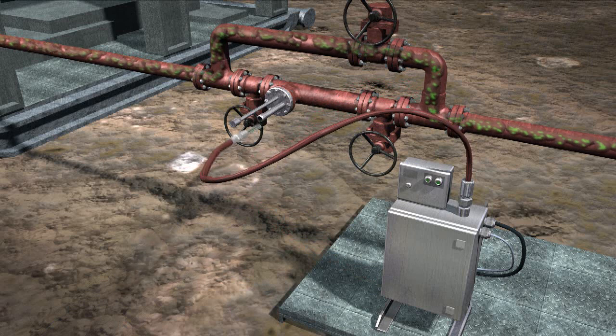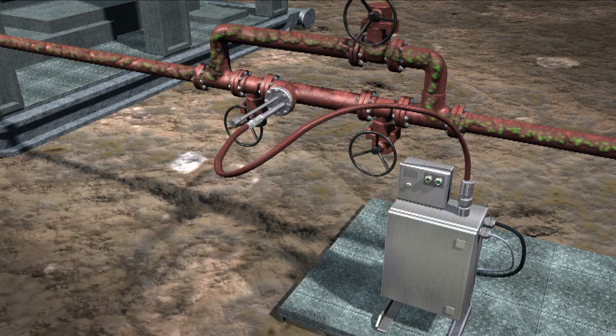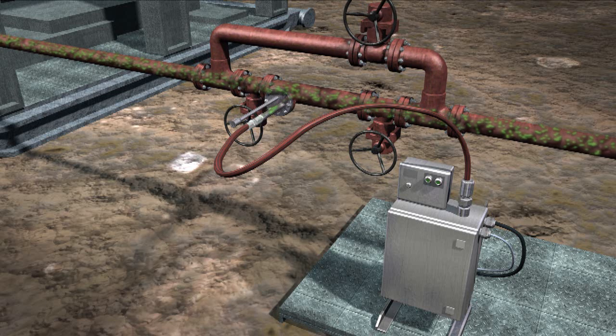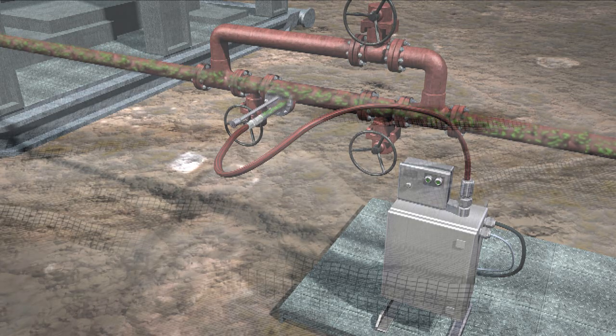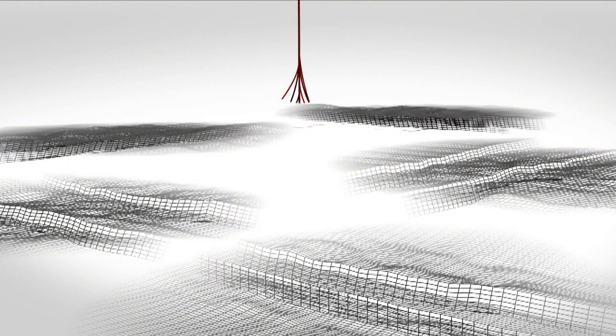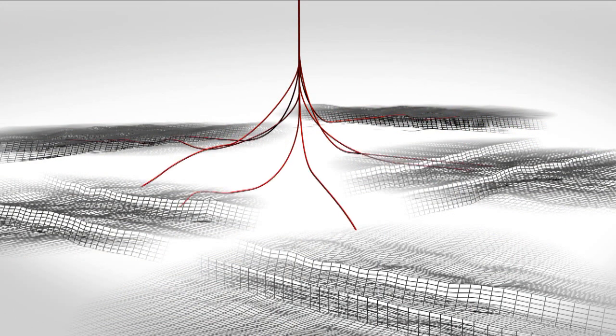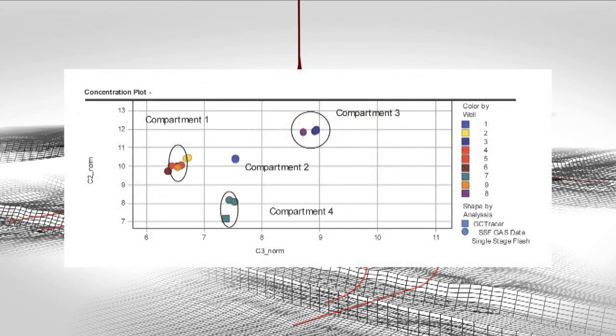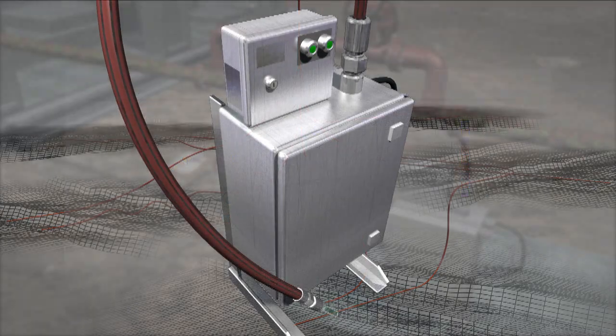The GCTracer can also be installed directly into the flow in closed systems, such as managed pressure and underbalanced drilling. For these systems, Weatherford has developed a custom-engineered bypass valve, which makes it possible to perform maintenance work on the probe without interrupting drilling operations. GCTracer can help you geo-steer and can indicate at which depths to take wireline fluid sample points. Its measurements can also be used in post-well analysis along with other parameters to reduce reservoir uncertainty.